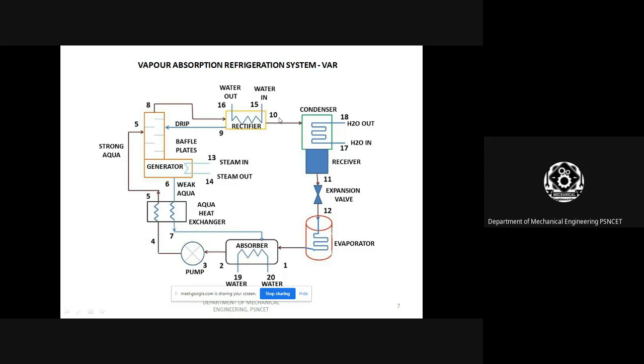How is the vapor refrigerant condensed into liquid? By a cooling process, by means of a coil with water circulated inside, that is H2O in and H2O out. The H2O in absorbs heat from the vapor, and it condenses into a liquid. That liquid is received in the receiver and then passed on to the expansion valve. The expansion valve expands it, so the temperature and the pressure are reduced. Then the cycle is repeated. This is the vapor absorption refrigeration system.